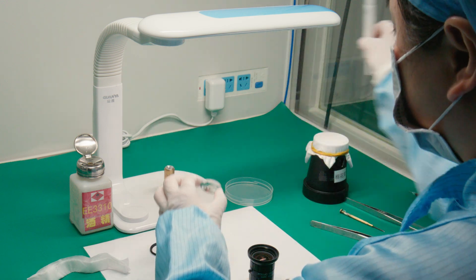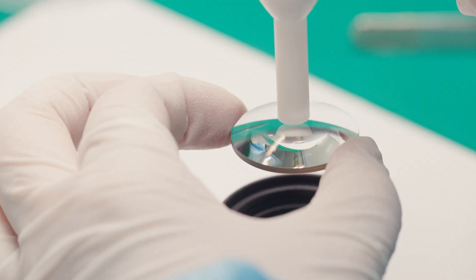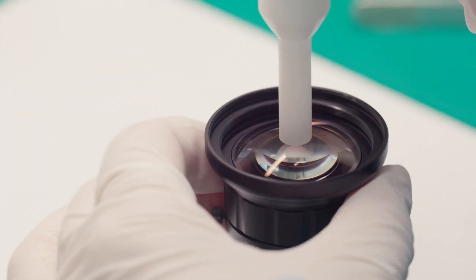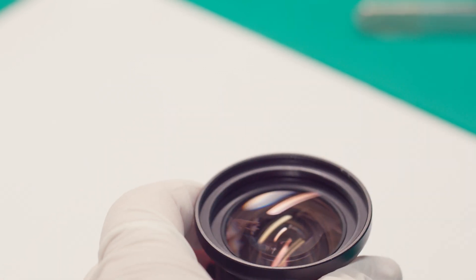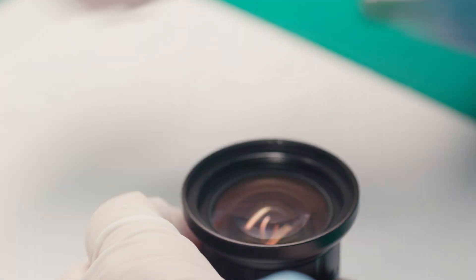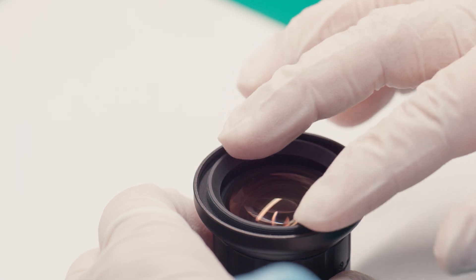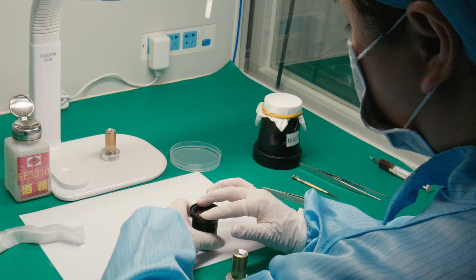Large lens elements require additional tools, like a vacuum chuck, to assemble them into their mechanical seat without tilt or de-center. Threaded retaining rings are also installed to secure the optics in place.